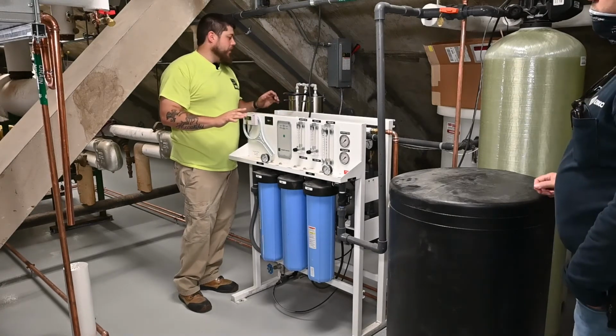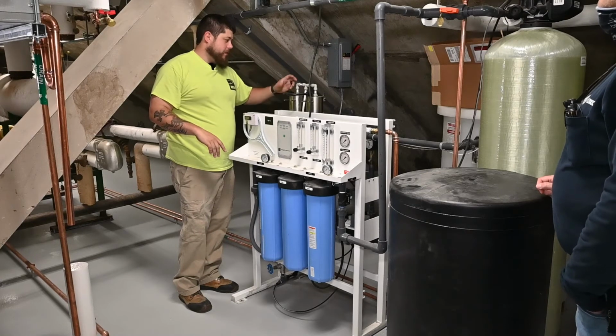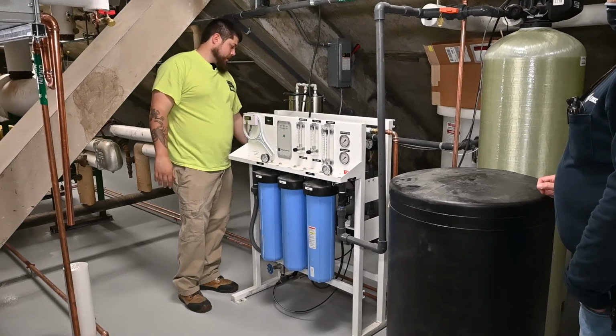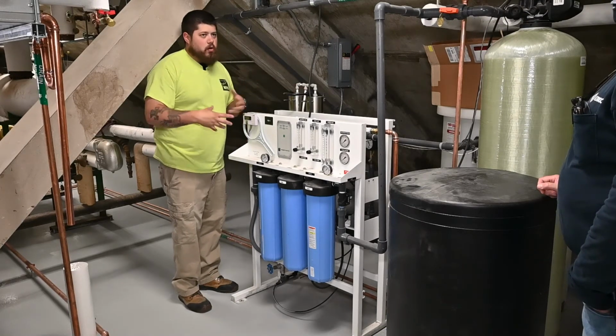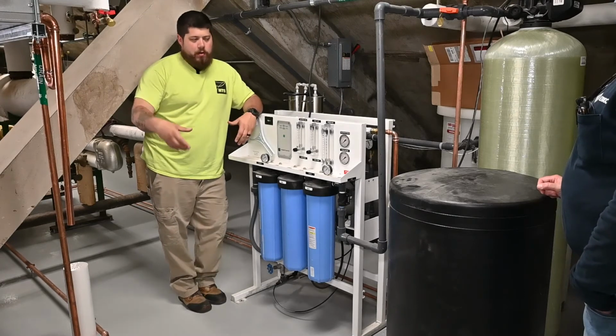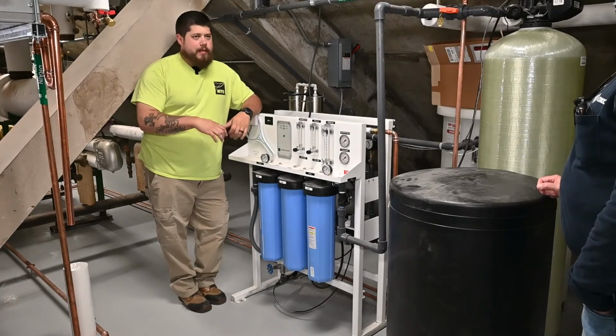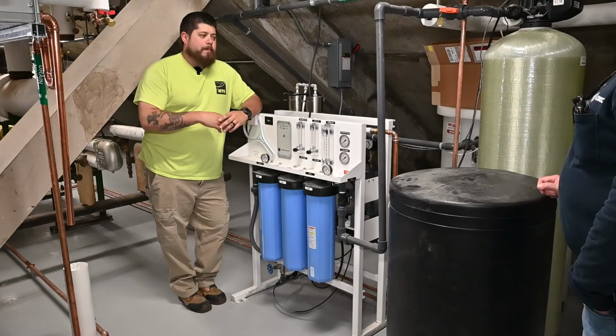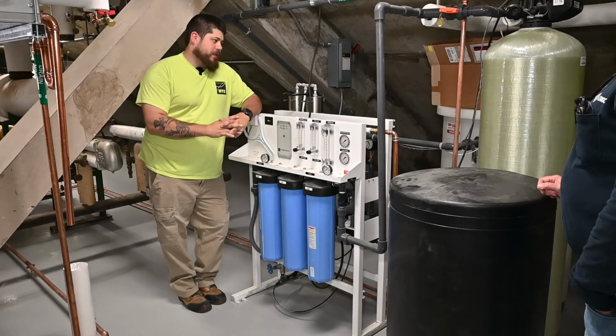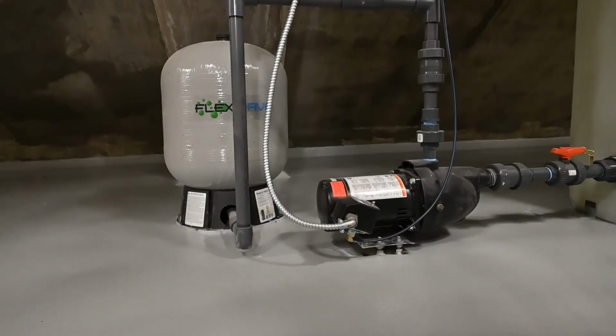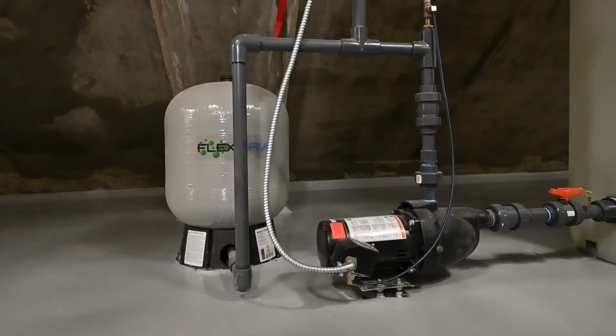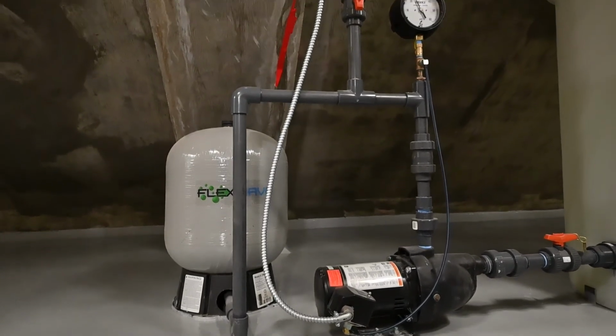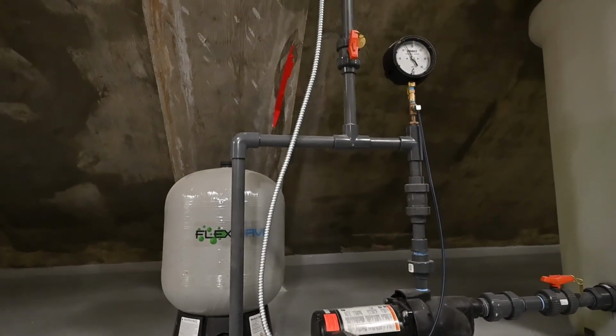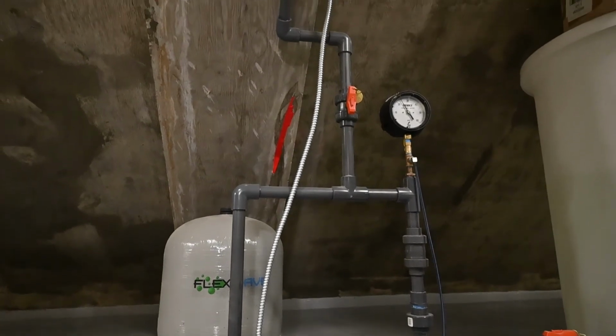The way I did it in general was just take this off here, unscrew right here, unscrew the bottom, and just take the whole thing apart. You can take the whole canister up, bring it over here, put it in a bucket, take it apart easy, make it easier on you, and replace the membrane. There's a pump down here. There are no grease spots on this pump. There's nothing that should have to get done to it.